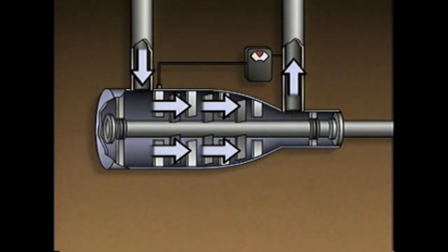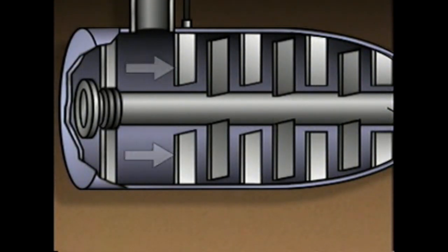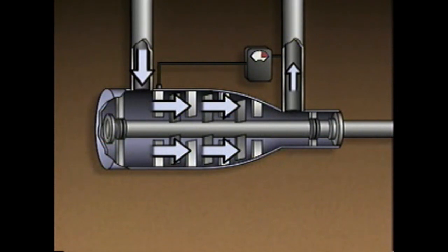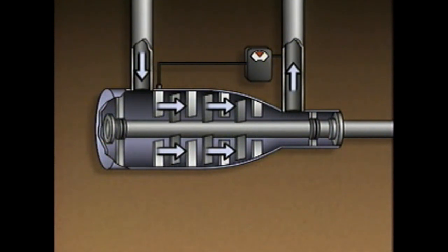On the other hand, if the demand for gas decreases, discharge pressure increases. The pressure controller responds to the increase in pressure by closing the inlet guide vanes. As a result, the flow of gas into the compressor is reduced, less gas is compressed, and the discharge pressure returns to the desired value. So by adjusting the flow of gas into the compressor, the control system maintains the discharge pressure of the compressor at the desired value.